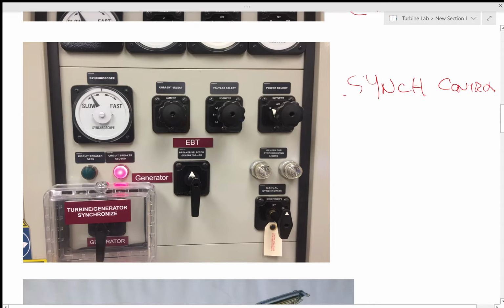So these are the controls. When you want to bring a generator up and put it online, you can operate it two ways: as that turbine only, or you can also piggyback onto El Paso Electric. The problem with running it alone is that if your turbine goes down, you have no other power to resort to. So we also piggyback onto El Paso Electric, and if our turbine goes down, El Paso Electric will immediately pick up all that lost power, if and only if our turbine is synced into their system.